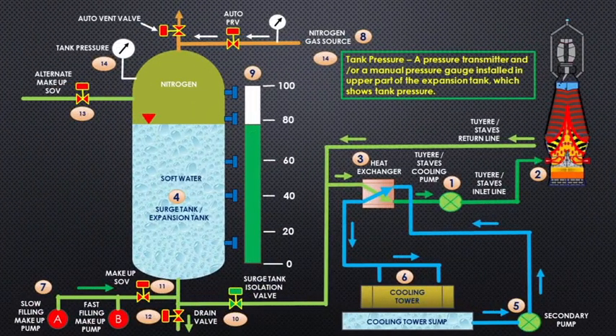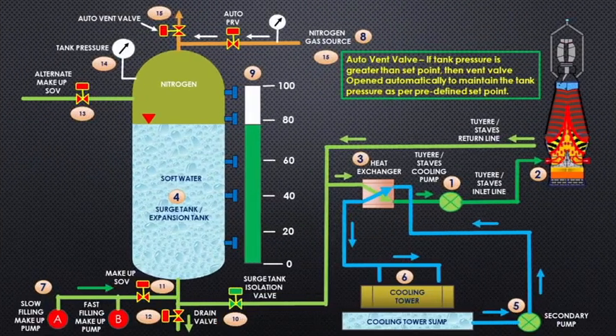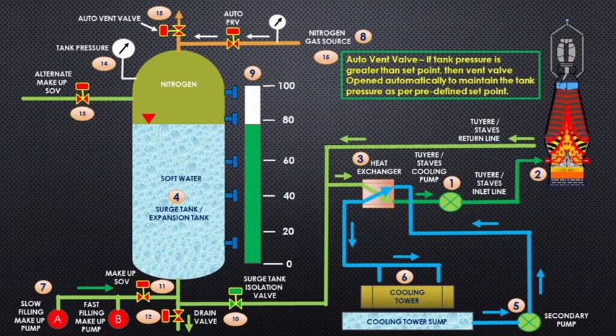Tank pressure: a pressure transmitter and/or a manual pressure gauge installed in upper part of the expansion tank shows tank pressure. Auto vent valve: if tank pressure is greater than set point, then vent valve opens automatically to maintain the tank pressure as per predefined set point.